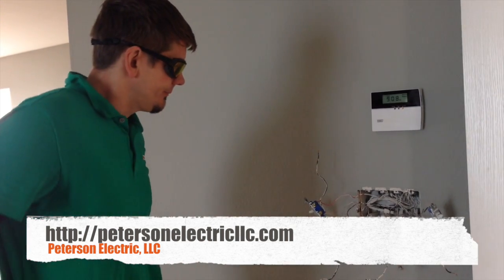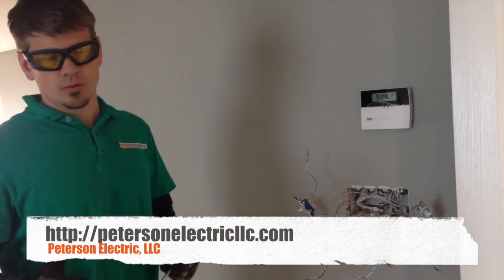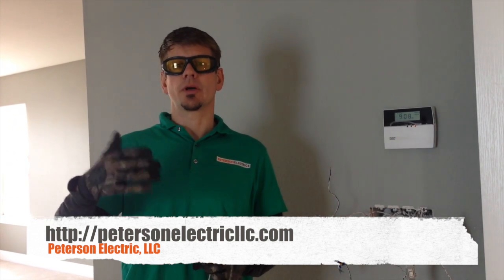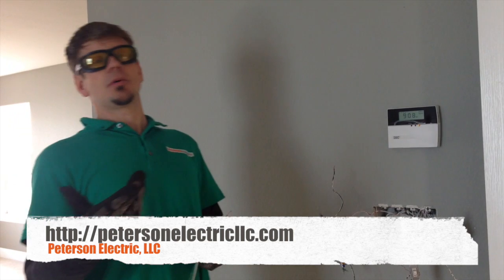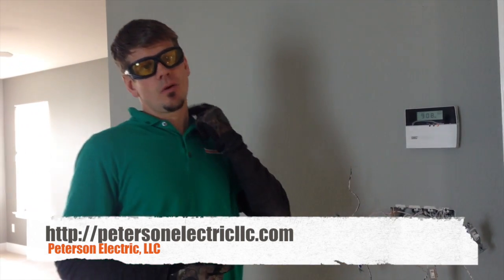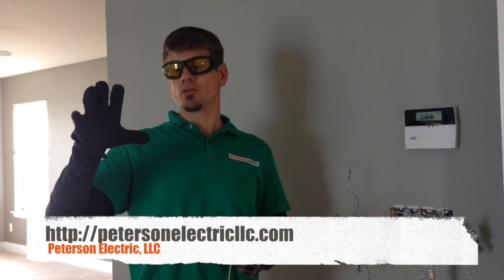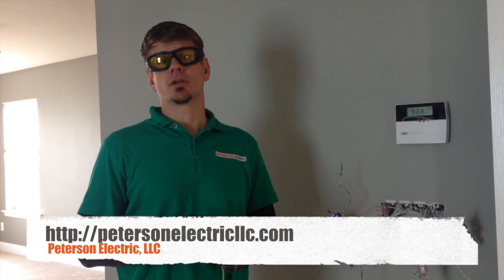So here's the thing. The original complaint was that the person buying the home saw that the painter was painting, and while she was here she heard or saw the breaker pop and his light go off, and then they couldn't reset it. That came up on an inspection report. When I heard the call over the phone, it sounded like the painter was trying to get the job done with a 1500-watt drop lamp going, and that might blow the breaker alone just because of the wattage.